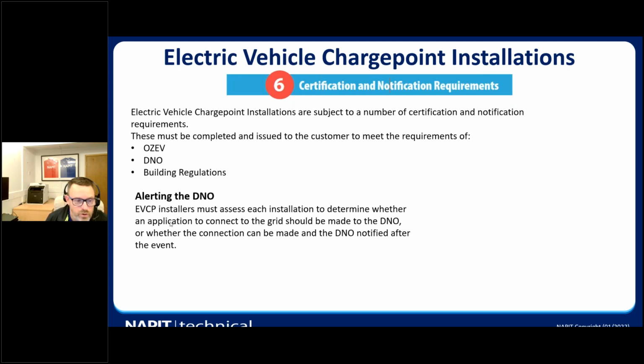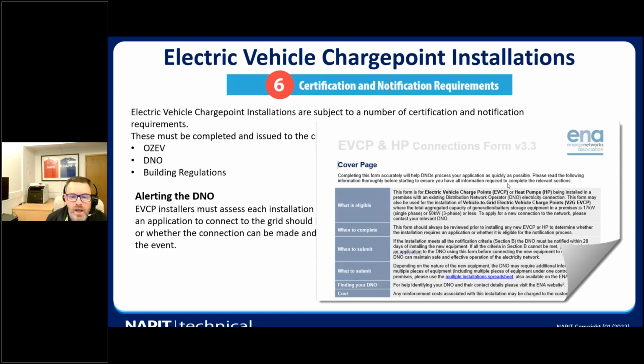So, alerting the DNO, obviously touched on earlier about the assessment of the installation. The previous table showed where the installer of the EV charge point must determine at what point the application must be made to the DNO and whether the installation is suitable for connection, or a DNO could be notified prior to or after the event of the EV charge point. And this is just an example of the form for the EV electric vehicle charge point, and it also does cover heat pump installations as well, but it tells you what should be done with it and can provide the information you need to notify the DNO before or after the installation of the EV charge point.